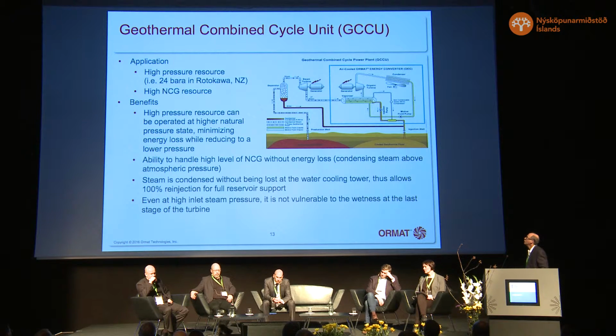A GCCU, geothermal combined cycle unit, first, as I said, enters the steam into a steam turbine. In that case, it can use very high pressure geothermal steam, 24 bars. It can also handle high NCG content.